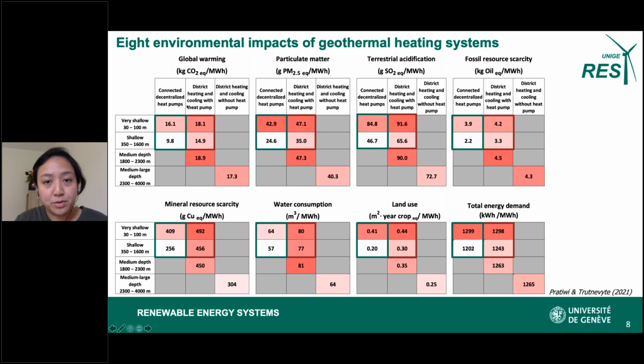What I observe here is that with a given depth, the impacts are smaller for the decentralized district heating than the centralized one. This is because in the decentralized network, the distribution temperature is lower, which allows us to use plastic-based pipes. Whereas in a centralized system, the distribution temperature is higher, necessitating steel-based pipes.